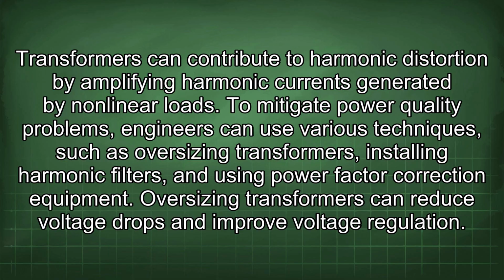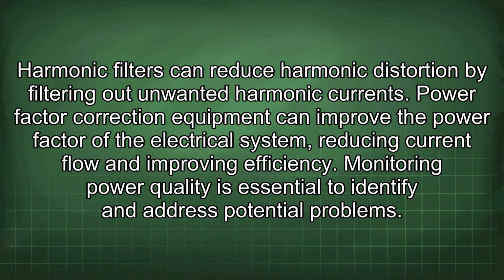To mitigate power quality problems, engineers can use various techniques such as oversizing transformers, installing harmonic filters, and using power factor correction equipment. Oversizing transformers can reduce voltage drops and improve voltage regulation. Harmonic filters can reduce harmonic distortion by filtering out unwanted harmonic currents. Power factor correction equipment can improve the power factor of the electrical system, reducing current flow and improving efficiency.